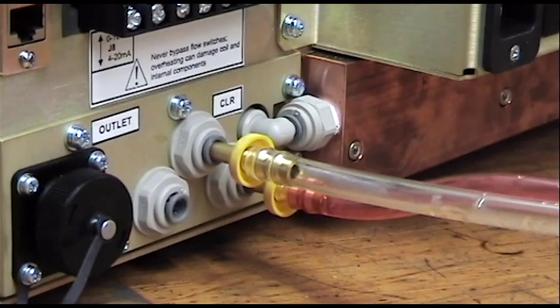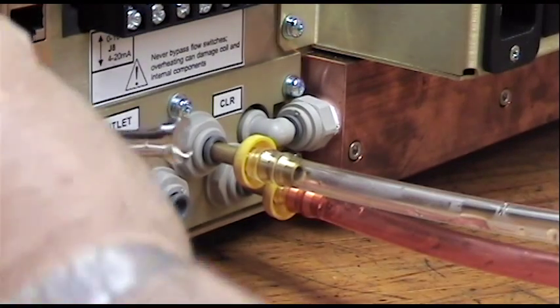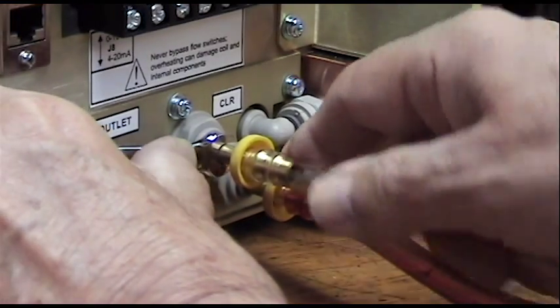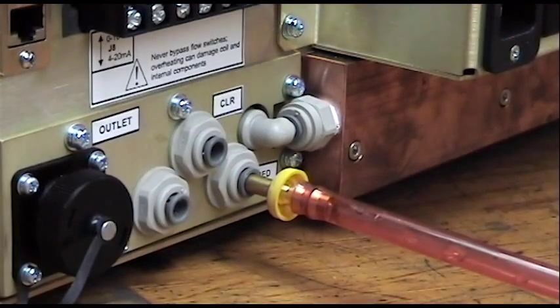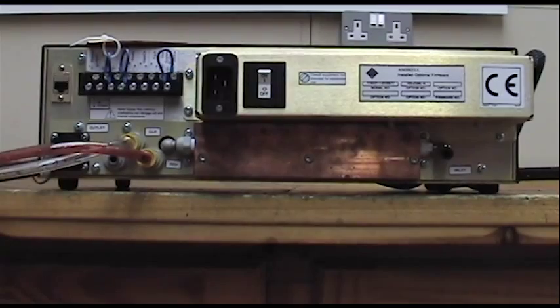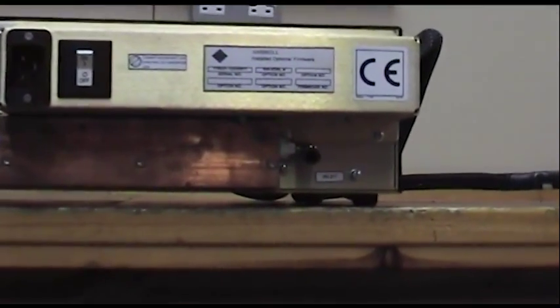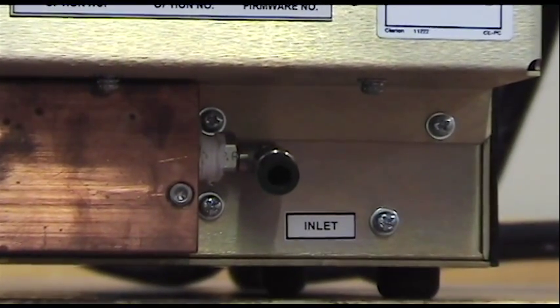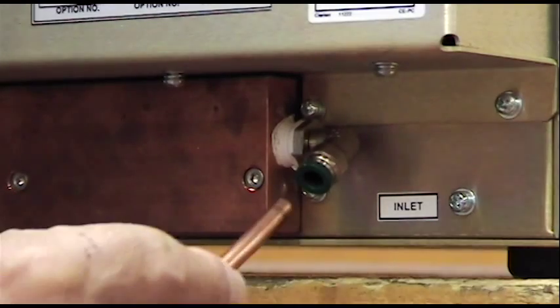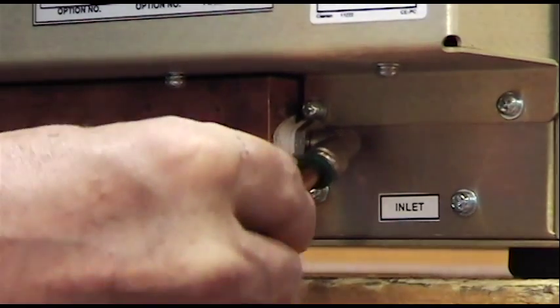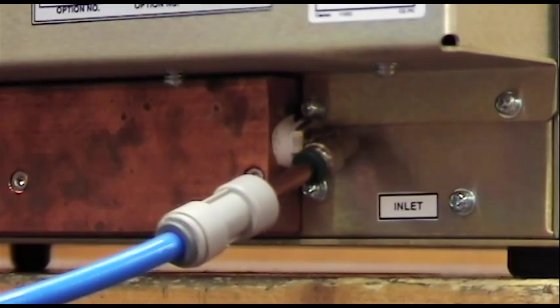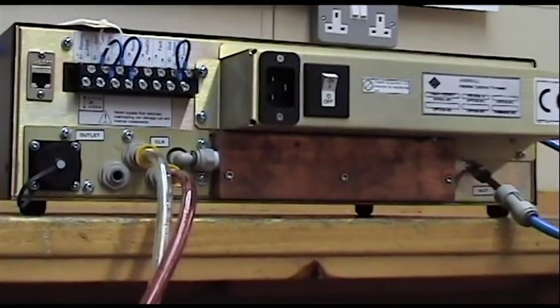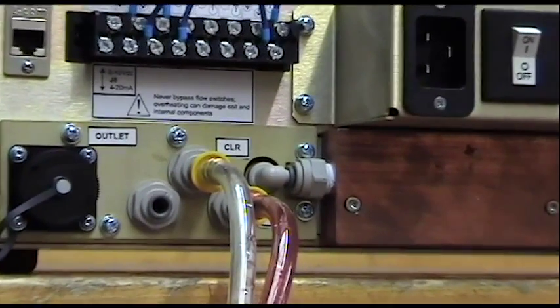When it is necessary to remove one of the tubes press the locking ring in with a suitable tool, for example a 7mm flat spanner and pull the tube free. The cold water to cool the inverter is fed first to the semiconductor heat sink and from there out to the workhead and coil. Connect the cold supply of water from the cooler to the inverter heat sink connector. The return water from the inverter to the cooler leaves via the connector to the left of the workhead connections.